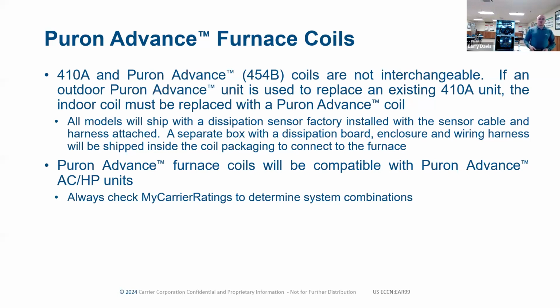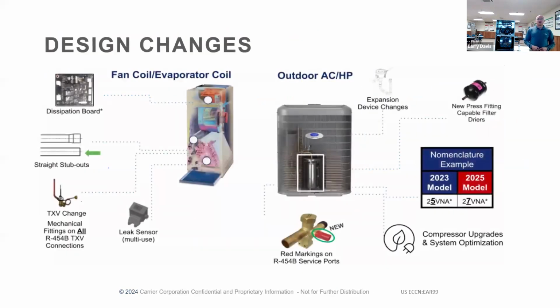So Puron Advanced coils only with the Puron Advanced 454B to 454B. Make sure you can get a rating in the ratings database for that matchup that you're putting together. So again, on our evaporators or fan coils, we have the dissipation board, we have the straight stubs, we have the new TXVs with mechanical fittings, the sensor that's in there. On the outdoor unit, you're going to see red caps versus the old black. That's going to be an indication of, hey, this is a 454B, along with the labeling on the unit. You will have the straight stub outs where you can use the press fit or the mechanical fittings versus brazing.